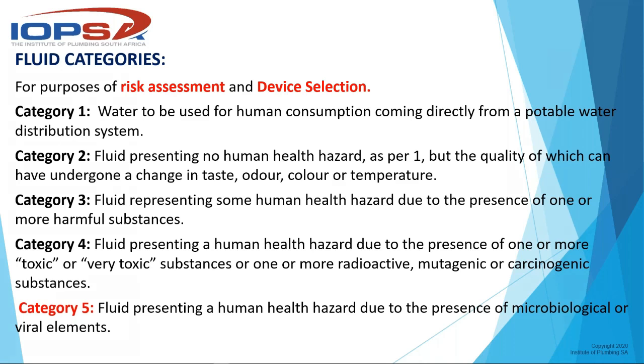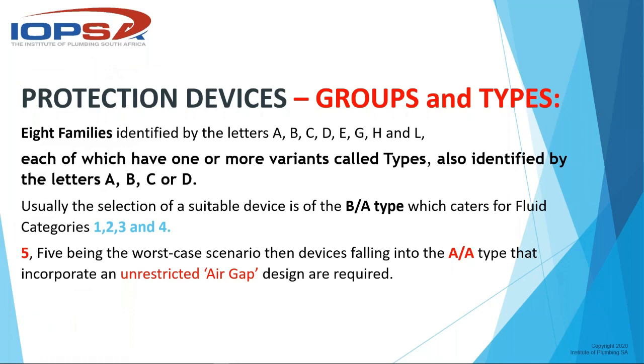Different backflow devices have also been grouped into eight groups — A, B, C, D through to L — depending on where they will be used. Usually the ones we will be dealing with is a BA type, which caters for all the fluid categories from one to four. That is the main one you guys will be dealing with — your standard BA type backflow preventer. For category five, you then have to have an AA, which is an unrestricted air gap — where there is absolutely no possibility of contact between the one installation and the other.